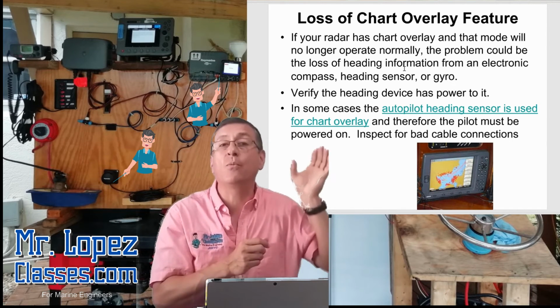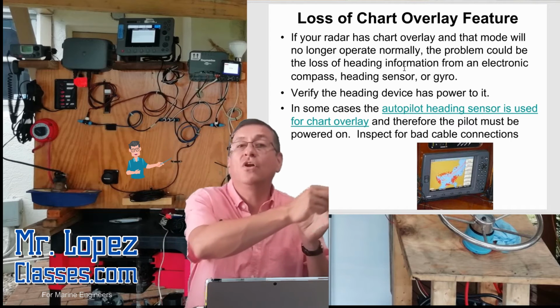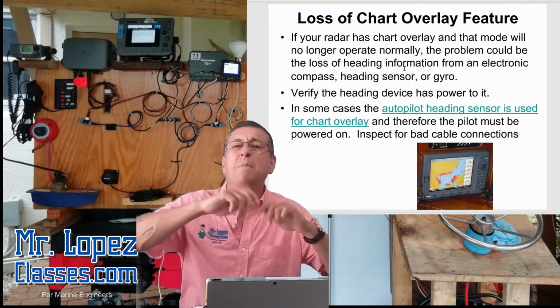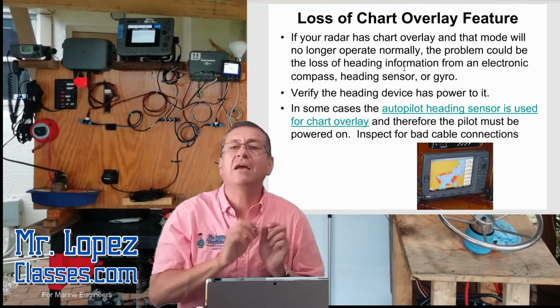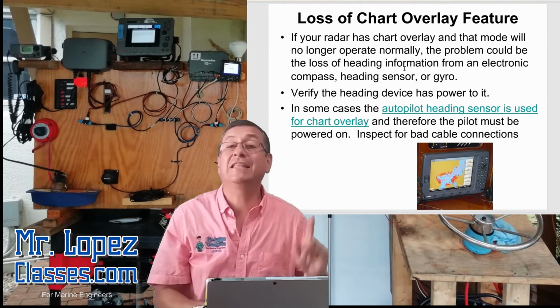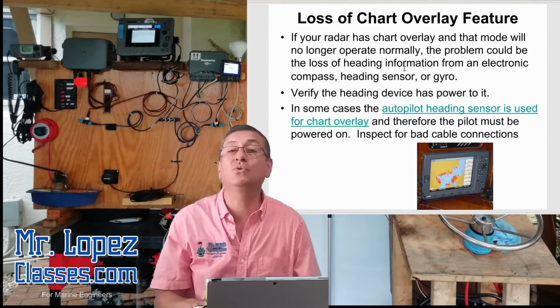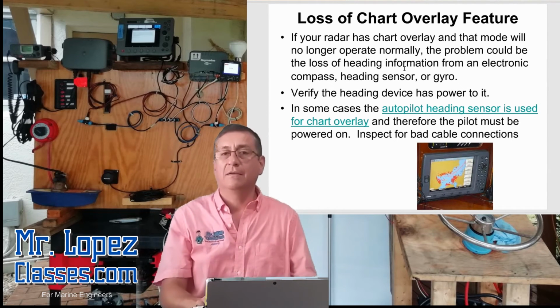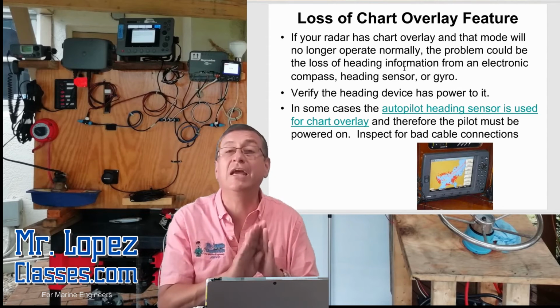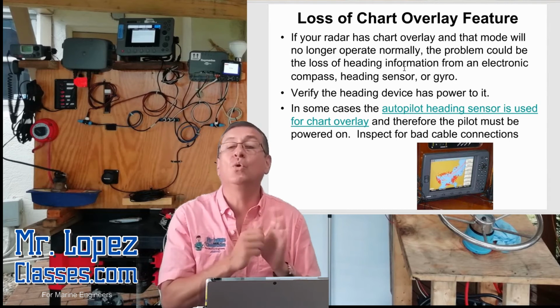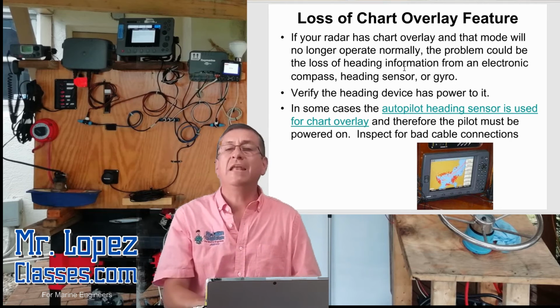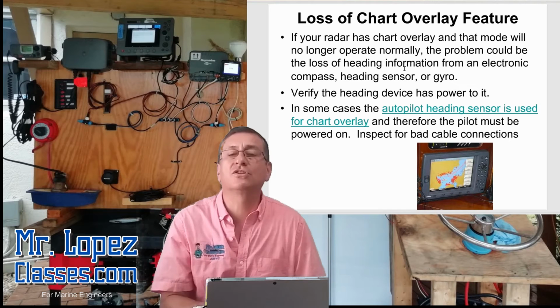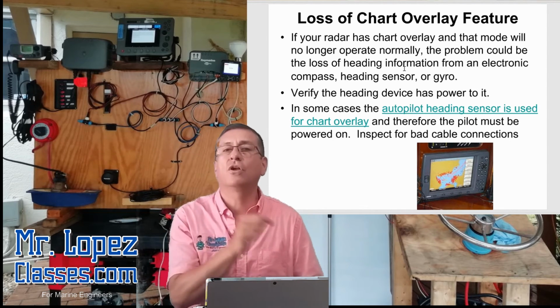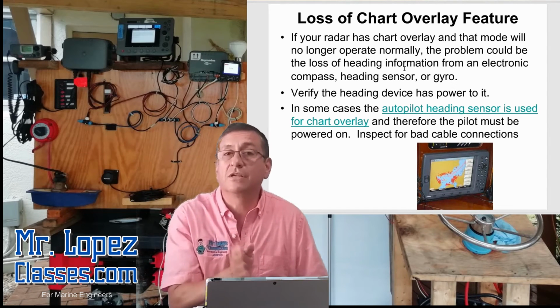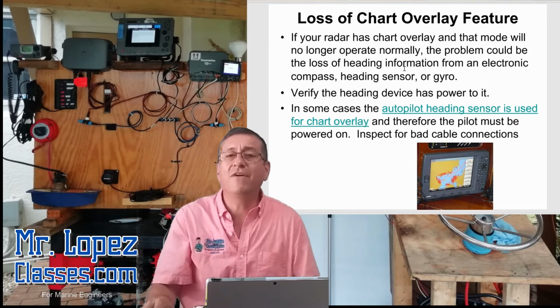Follow the sender cable between the sensor and the computer, and verify it's not bent, kinked, or broken, and is properly routed. Verify that cable is not close to the antenna cables, like the VHF antenna, and is not together with AC cables or close to bonding lightning conductors. Verify the conductor is isolated from other sources of power. That's very important, it's critical for that sensor, same as for the radar sensor, but especially critical here.